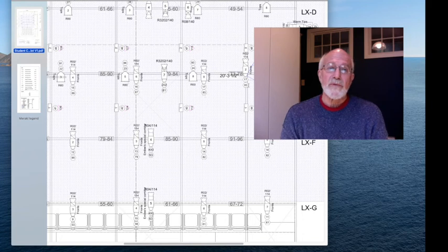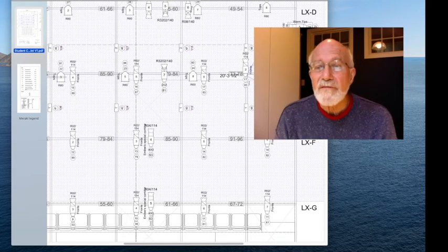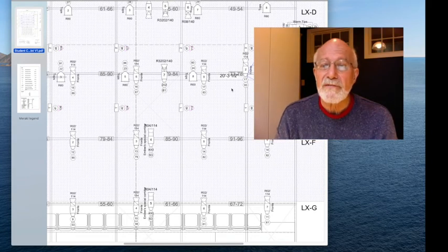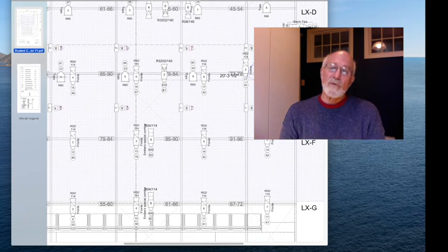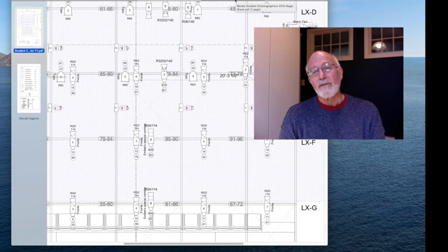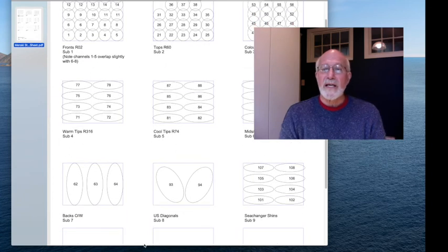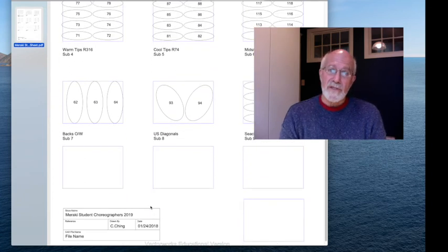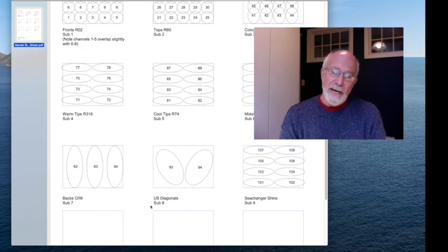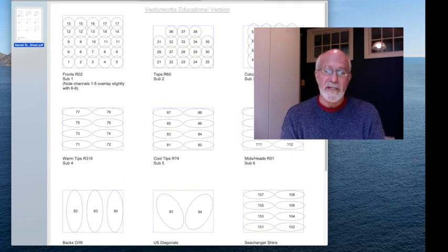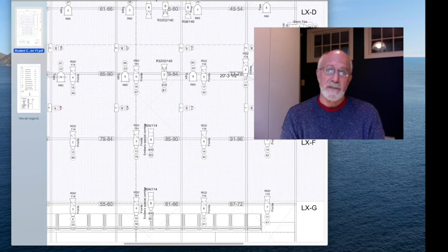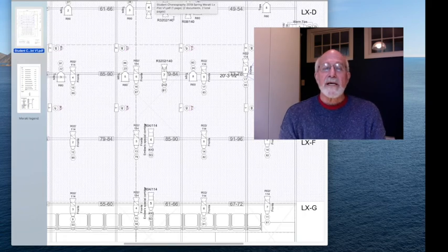And what this represents, on the other hand, these numbers in the hexagons, that's just pure convenience. What's available, the nearest available circuit that is not otherwise in use, that I can plug this instrument into, and then later when I'm setting up my control system, I can create a pattern of organization that makes it easy for me to go ahead and design, right?